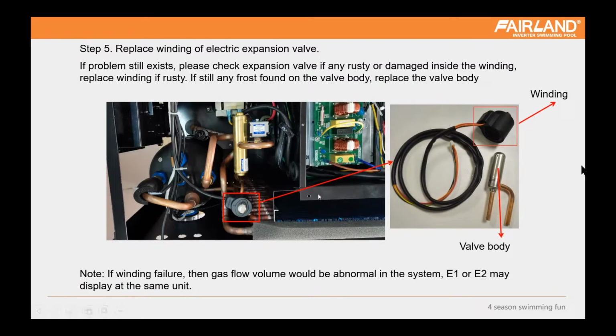And step 5, we will check the regulator. For the regulator, we set an electric expansion valve. This valve has a winding here. It's easily dismantled, removed by your hand, and you can check the winding inside to see if it is rusted. In some special situations, with very wet air, after 1 to 2 years, it is rusty inside. So maybe you can try to replace this winding to see if the unit will run normally.